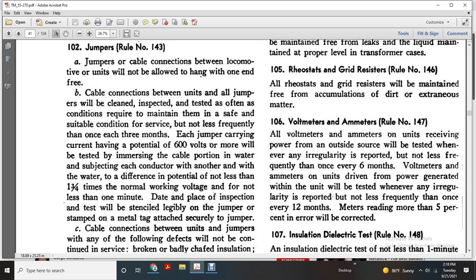106, voltmeter and ammeter, rule number 147. All voltmeters and ammeters of units that receive power from outside will be tested whenever irregularity is reported, and not less frequently than once every 6 months. The voltmeter and ammeter of units that generate their own power will be tested whenever irregularities are reported, and not less frequently than once every 12 months. Meter readings with more than 5% error will be corrected.